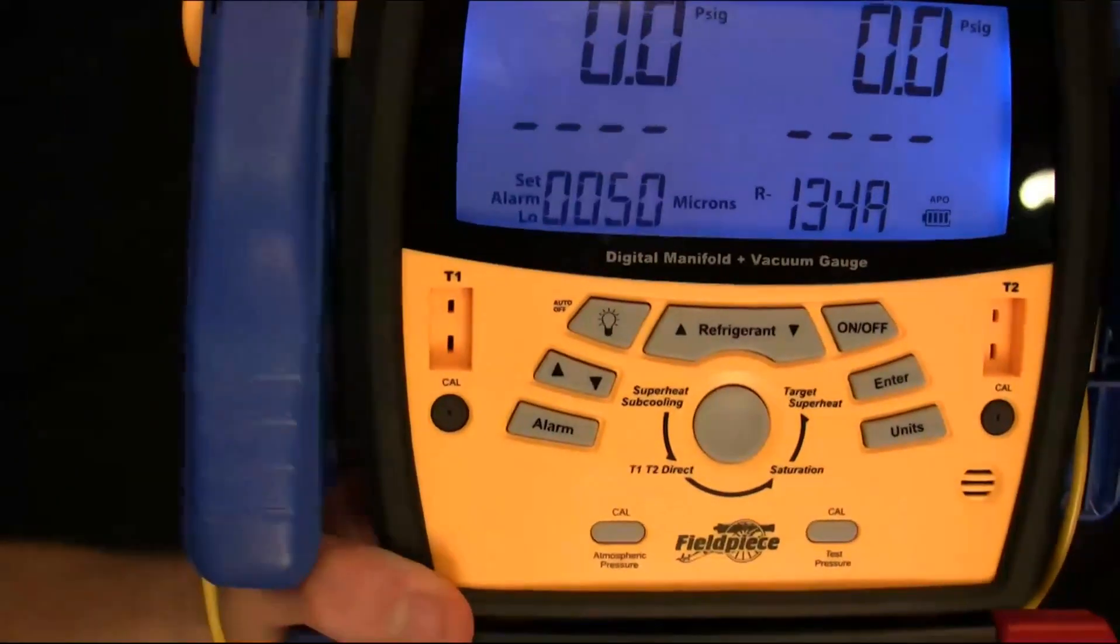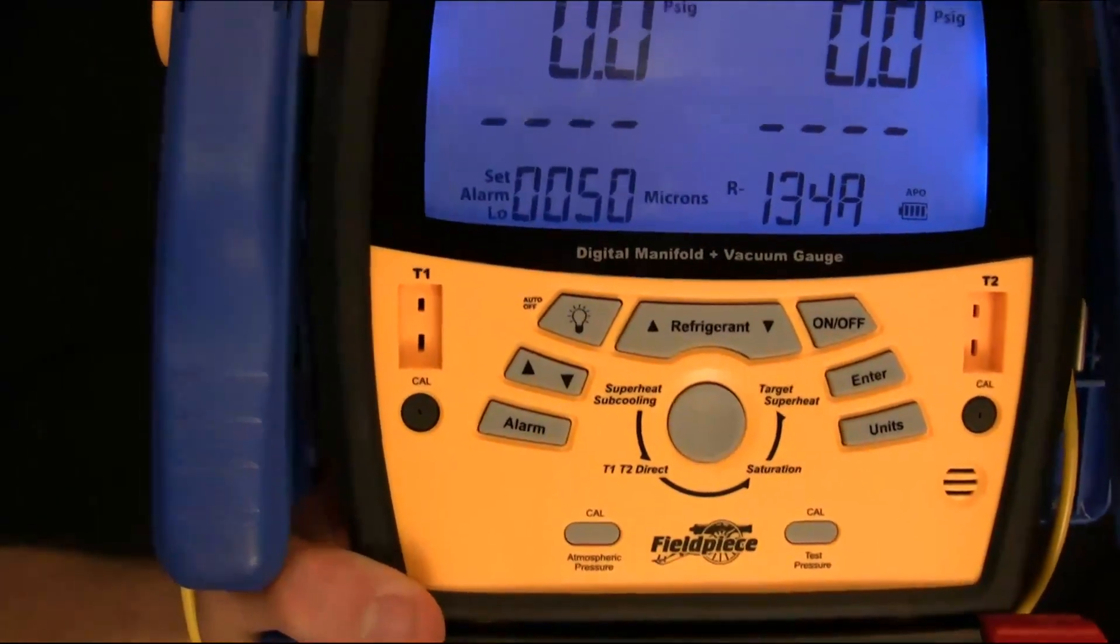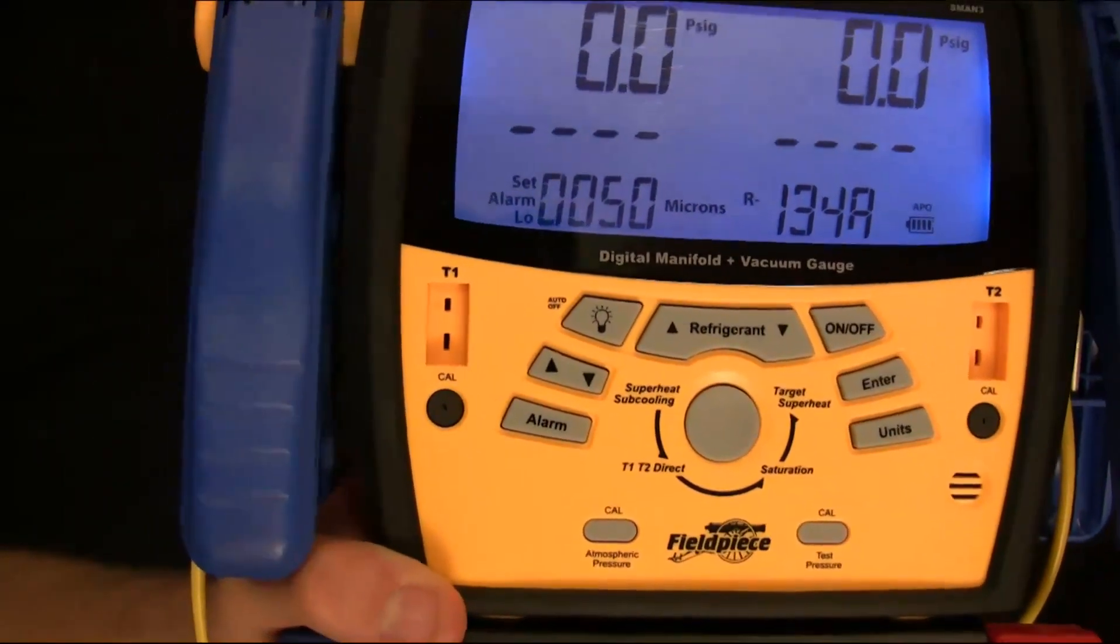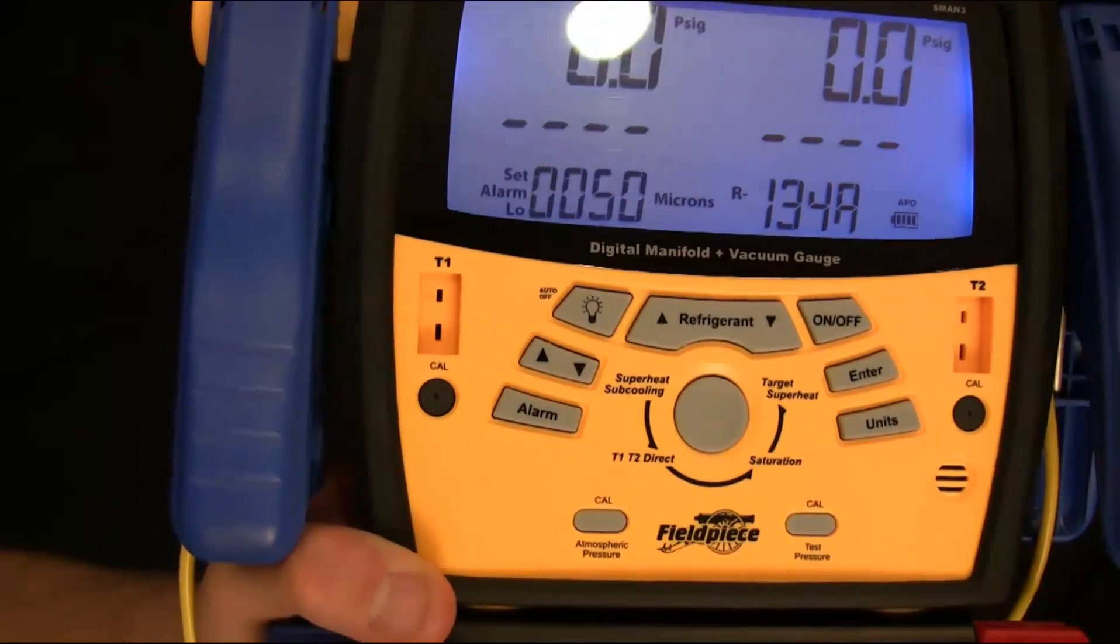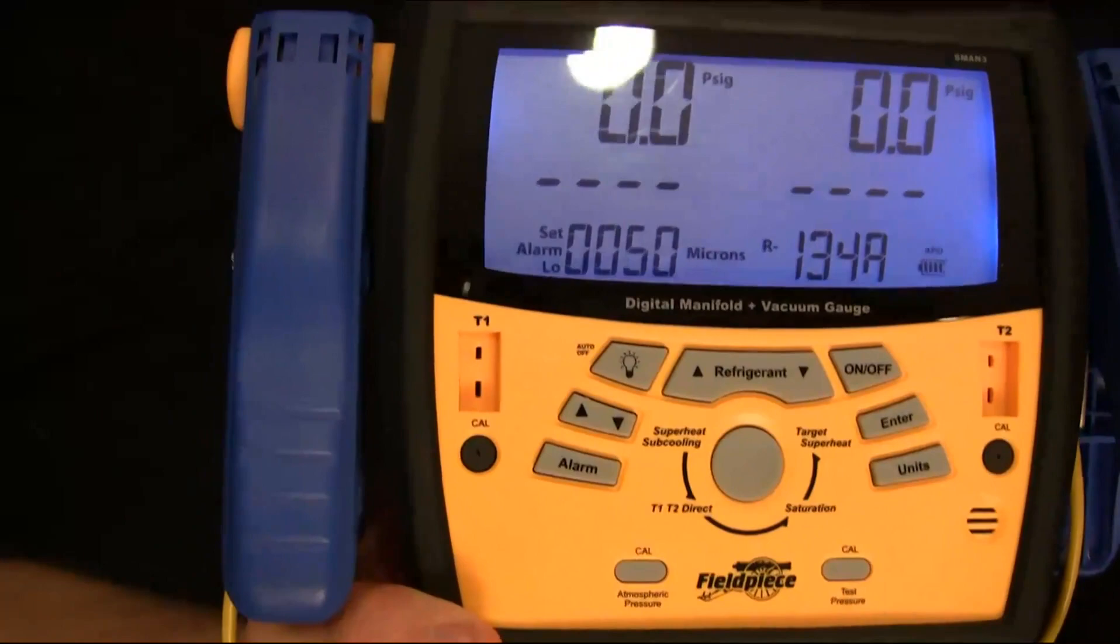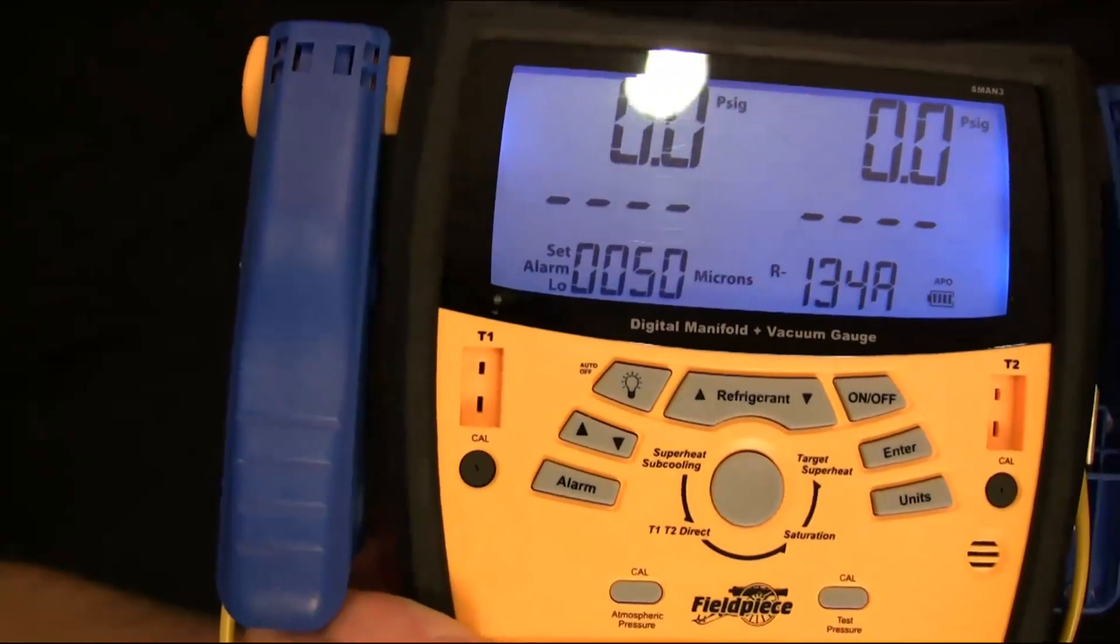What this does is as I start pulling a vacuum, I can set an alarm so that when it hits 50 microns, the alarm will go off. That way you don't have to babysit the system and you can be in your truck or whatever and the loud alarm will go off. And as long as you're close enough to hear the alarm, you'll know that your vacuum is done.